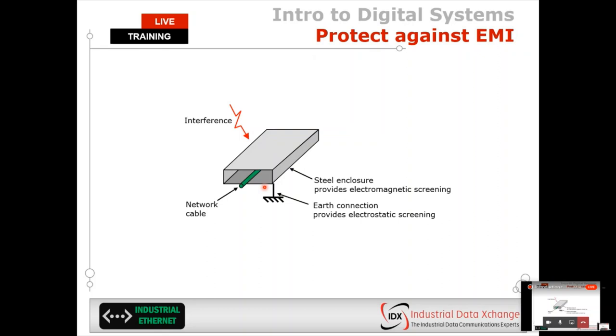One way which can protect from both electrostatic and magnetic interference would be running your communication networks or industrial Ethernet cable inside steel or aluminium trunking or conduit, but it's very important that the conduit is grounded at multiple different points. Otherwise this will serve no form of protection whatsoever.